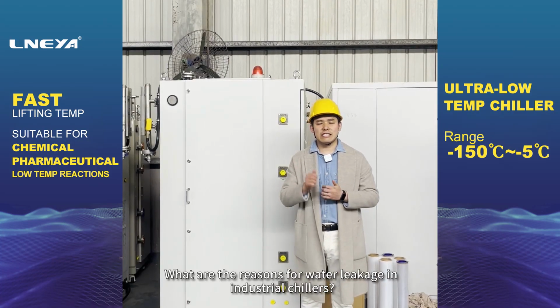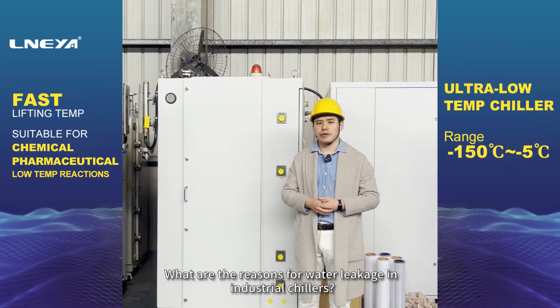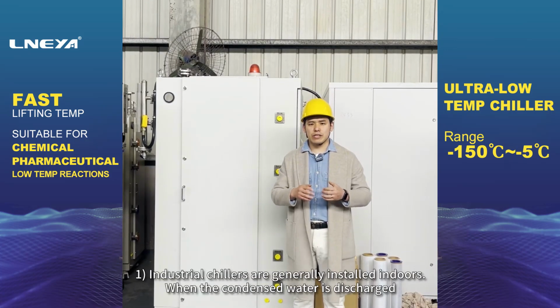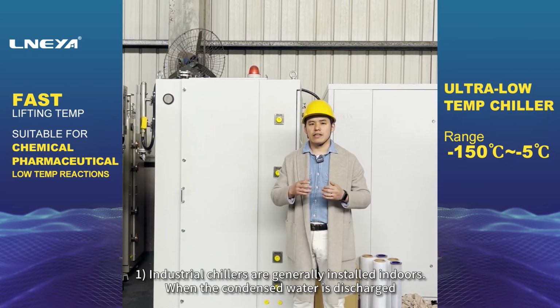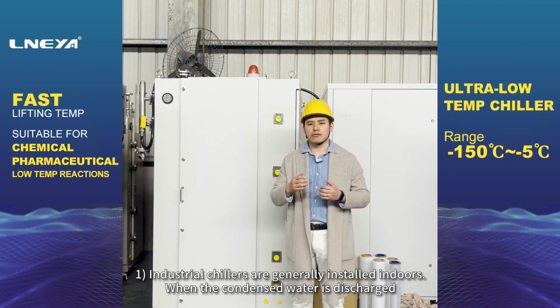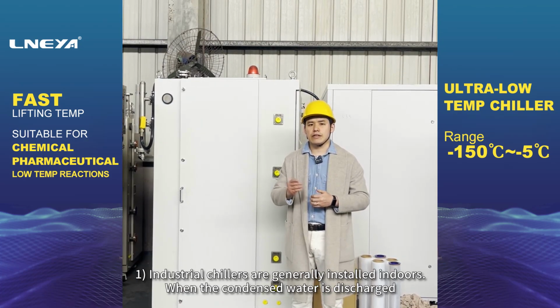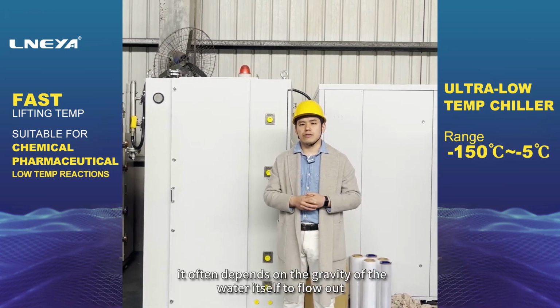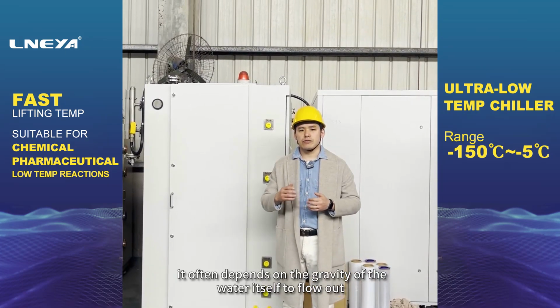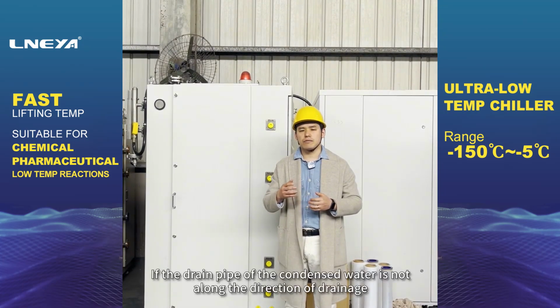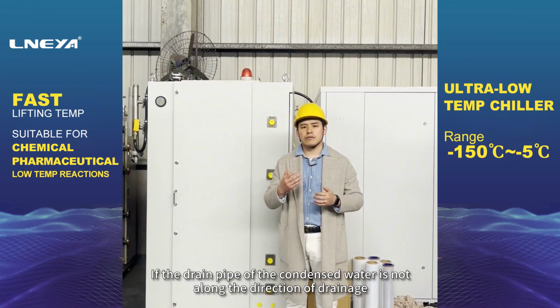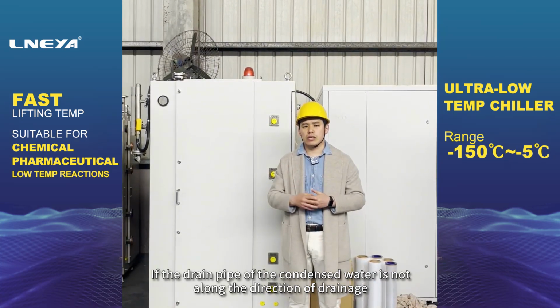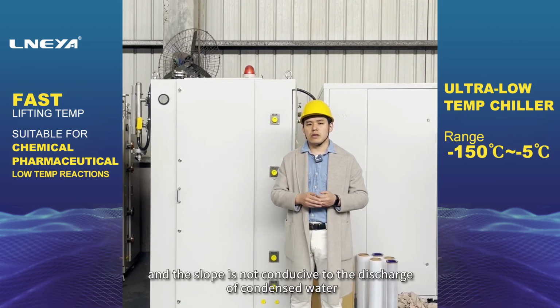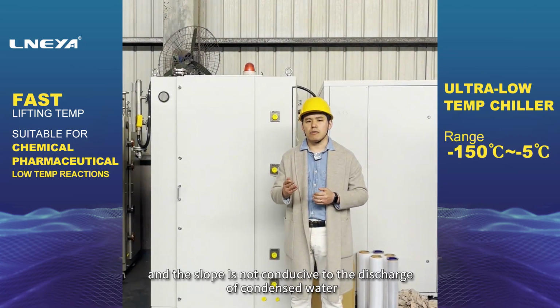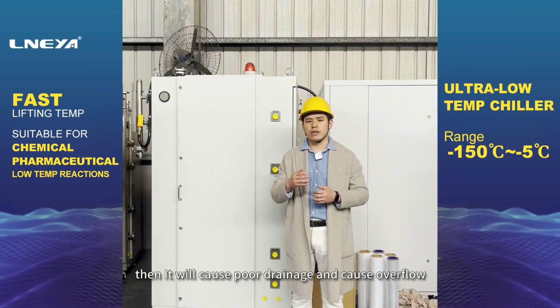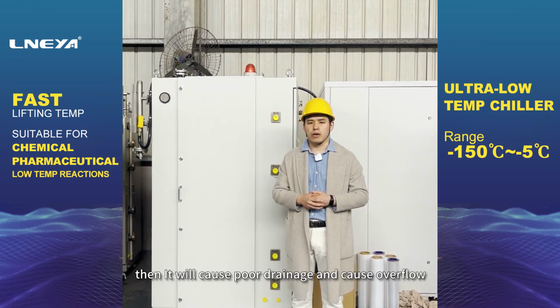What are the reasons for water leakage in industrial chillers? 1. Industrial chillers are generally installed indoors. When the condensed water is discharged, it often depends on the gravity of the water itself to flow out. If the drain pipe of the condensed water is not along the direction of drainage, and the slope is not conducive to the discharge of condensed water, then it will cause poor drainage and cause overflow.